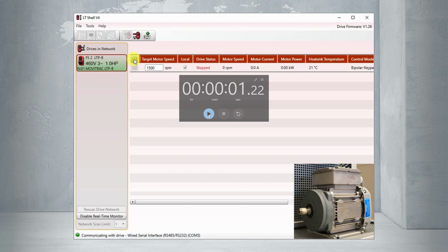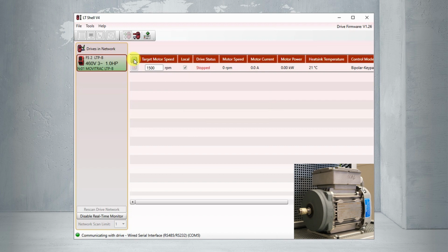And I'll just mention as an aside, my VFD never actually completely powered down. The filtering capacitors inside were able to keep it up, so it was able to complete that ramp, and when I turned the power back on, it just resumed normal operation. Of course, it didn't restart the motor because we weren't in ride-through mode. It did ramp it to a stop, bring it to an orderly halt, and now it's just waiting for me to tell it what to do.